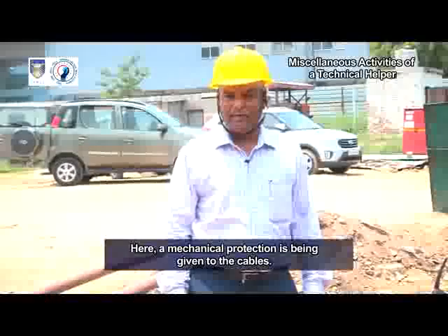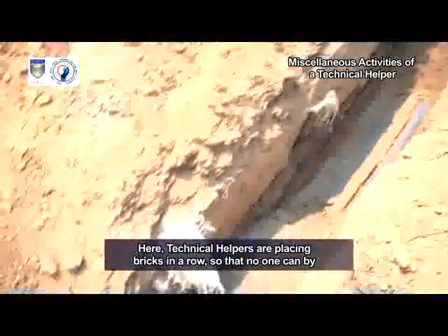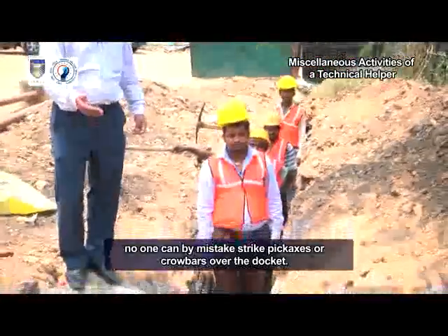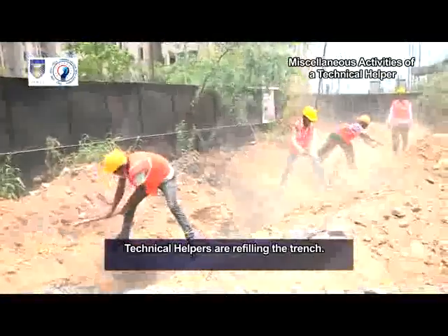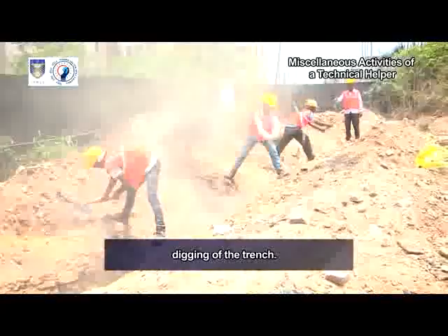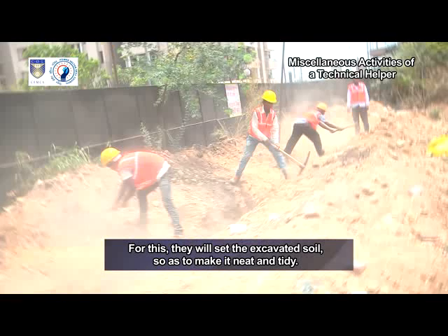A mechanical protection is being given to the cables. The sand bed will be covered with brick or RCC docket. Technical helpers are placing bricks in a row so that no one can by mistake strike pickaxes or crowbars over the docket, and the HT cables thus remain protected from any damage. Now the refilling of the open trench begins. After completing the docketing, technical helpers are refilling the trench — first the soft soil and then the hard soil excavated during the digging. They will ensure that the complete area is in its original form by setting the excavated soil to make it neat and tidy.